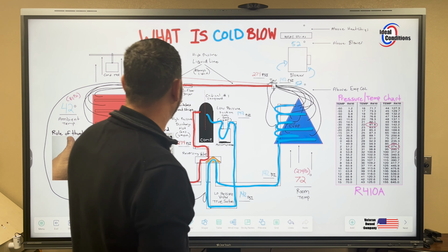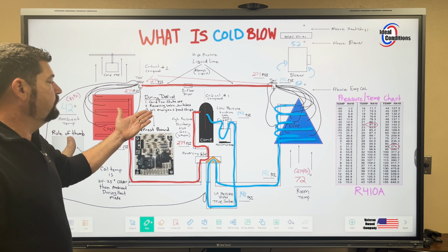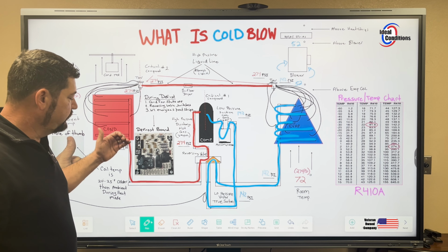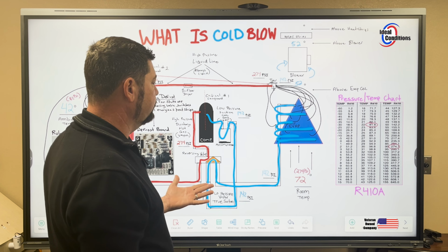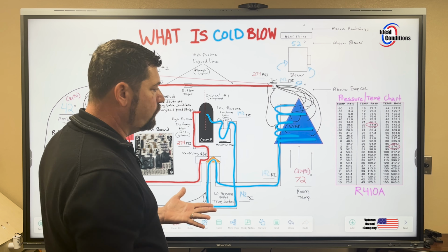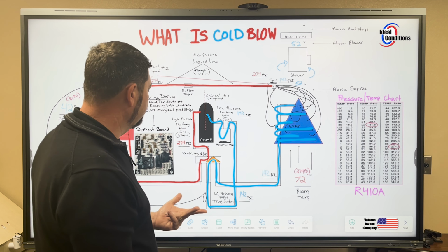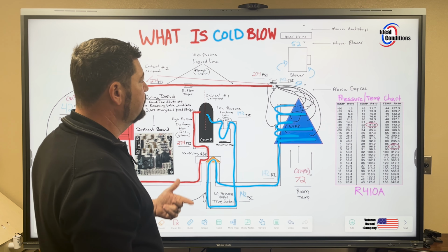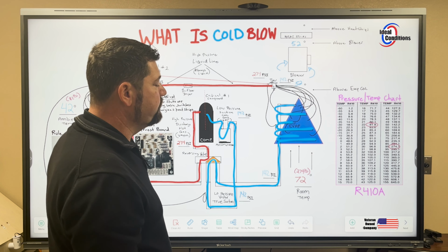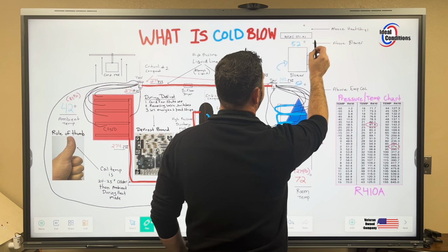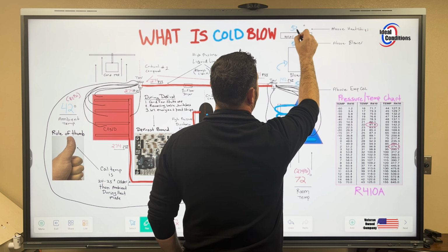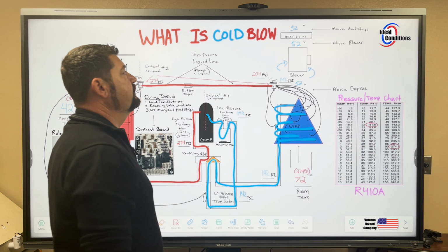And if these heat strips never came on because the W2 was never energizing my strips, either because the wire was not connected right, or W2 wasn't energized because the board was bad, or the heat strips aren't working properly, any scenario you could possibly think of, then now I have 52 degrees coming out of the top into my plenum.